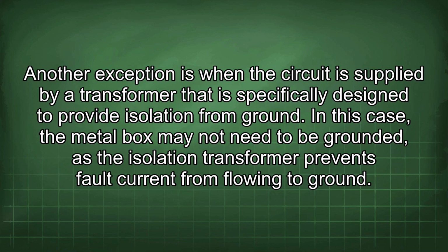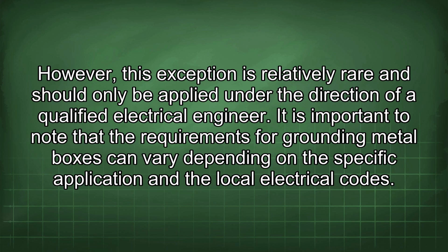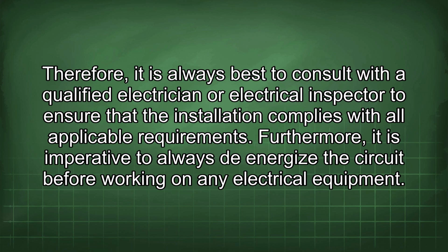Another exception is when the circuit is supplied by a transformer that is specifically designed to provide isolation from ground. In this case, the metal box may not need to be grounded, as the isolation transformer prevents fault current from flowing to ground. However, this exception is relatively rare and should only be applied under the direction of a qualified electrical engineer. It is important to note that the requirements for grounding metal boxes can vary depending on the specific application and the local electrical codes.